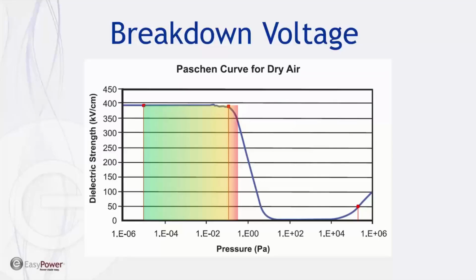As you pull a vacuum, you can see that a very slight vacuum actually has very poor insulating ability. If you've ever tested a vacuum interrupter that failed and you can't even apply voltage to it, I've had some that wouldn't allow me to apply even 1,000 volts. In that case, the pressure inside the vacuum interrupter is somewhere in that very low range, just below atmospheric pressure. But if you continue to decrease in pressure, increase in vacuum, there is a drastic increase in the insulating ability of the vacuum or of dry air, starting around 10 Pascal and continuing to increase to around 0.1 Pascal, or 1 times 10 to the minus 1 Pascal.